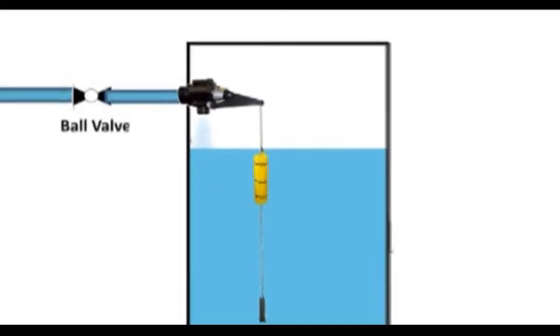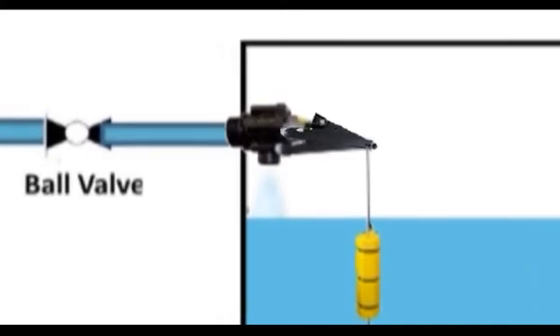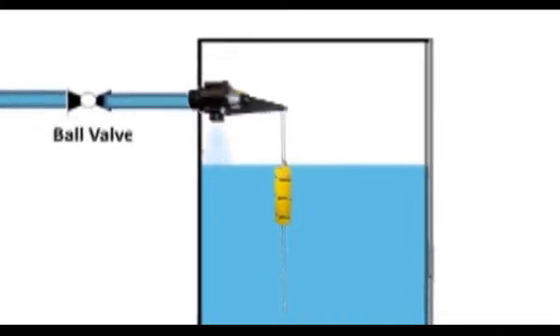Once float reaches to maximum level, weight of same will be nulled and differential float valve will be closed. Once valve is closed, water delivery will be stopped and pressure in pipe will get increased.